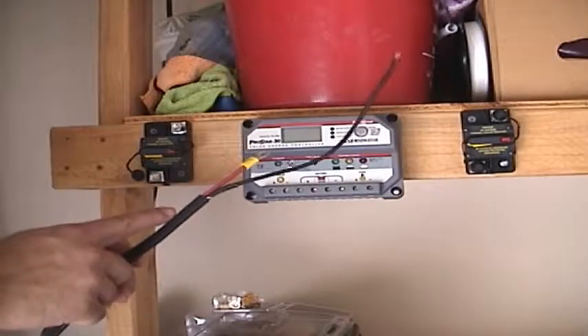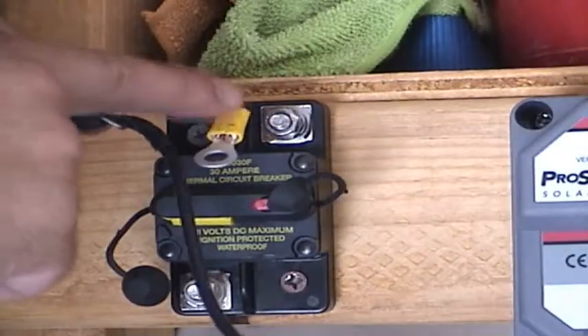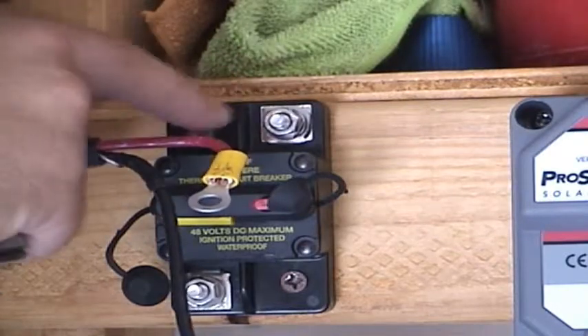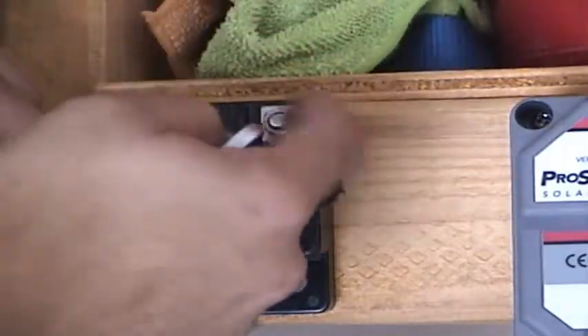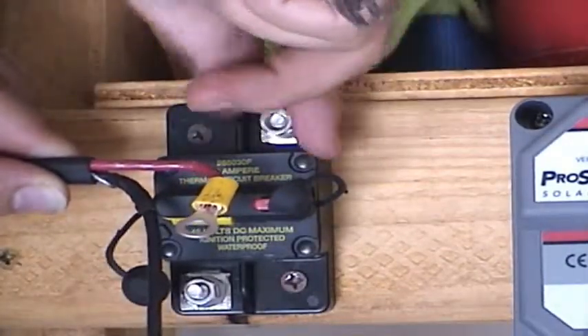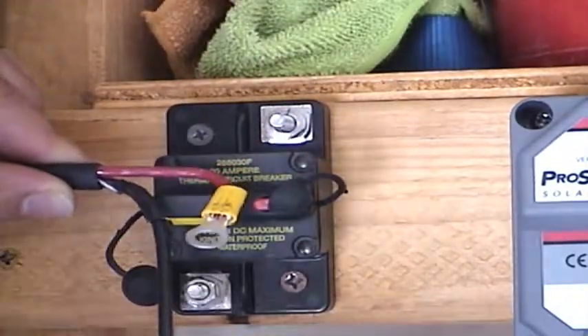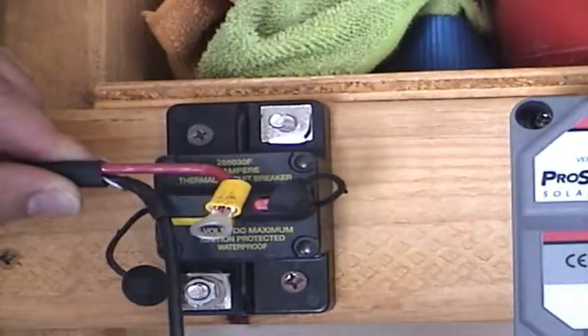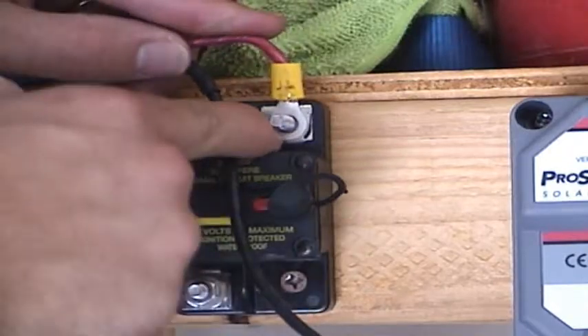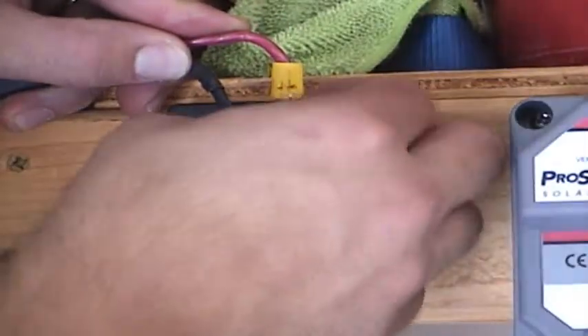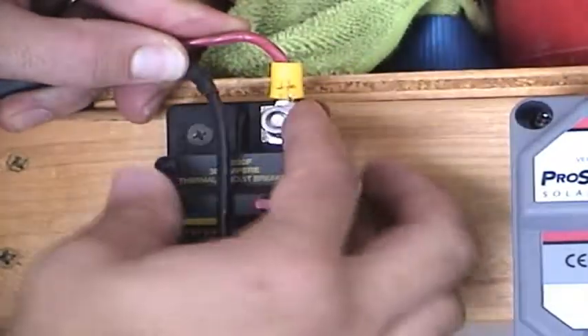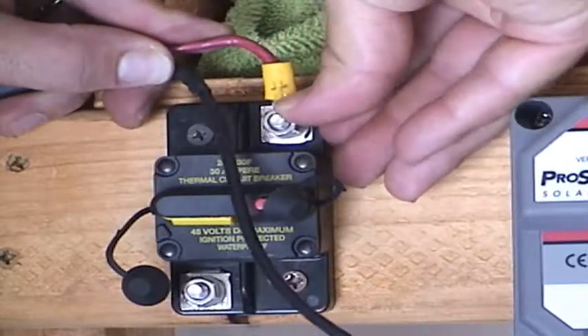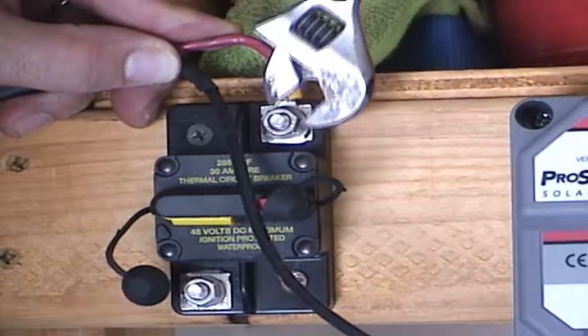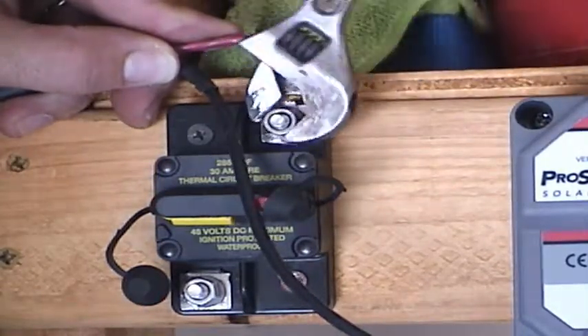Okay. Now we're going to take the outdoor cable coming from the solar panels that we just cut, and let's connect the red tail to the top terminal on the circuit breaker that's marked tab on the side. Go ahead and get our wrench, and we will loosen the screw. Remove the lock washer. Go ahead and insert the ring terminal. Replace the lock washer and replace the nut. And then tighten the nut back down as tight as it will go.